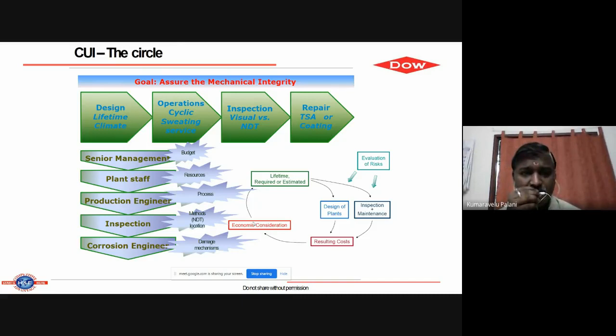So all these things were fulfilled by the Dow company. But why did it fail? Because if equipment or piping is not registered, it will not be inspected. The chosen strategy is an operative failure. That specific equipment or piping was not properly registered and so it was not inspected, because the contractor took care of the design and the specification of the material. So ownership was not taken by the Dow team. So it is one of the operation failures.